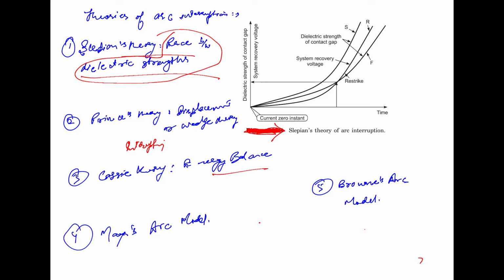Now next is the Cassie theory. Right from the early days of the development of circuit breakers, it was observed there is much more to successful arc interruption than the simple race between the dielectric strength as given by the Slepian's theory. There is much more to it than a simple race between the dielectric strength of the contact gap and the recovery voltage. So the energy balance theory was introduced.